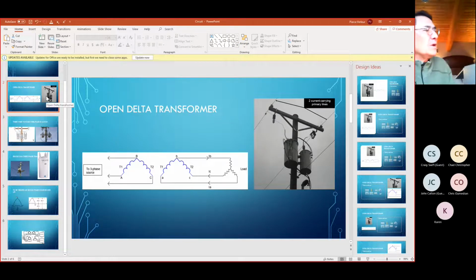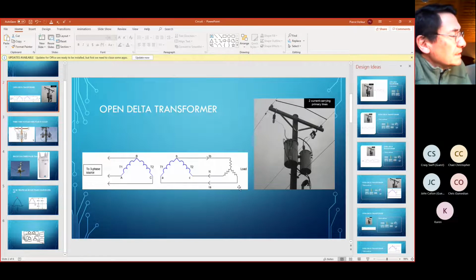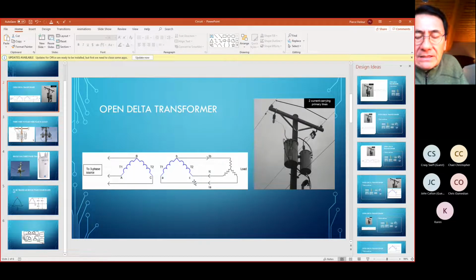Open delta transformer. When you identify that you have an open delta transformer, and typically it's going to be a 2-can system off of the power pole. It can be a single can system if the can, you can see that there's only 3 lines coming off of this and 2 windings. This is an unbalanced 3-phase system, and the imbalances increase as you increase the load.